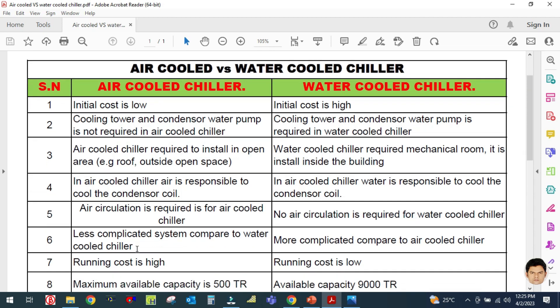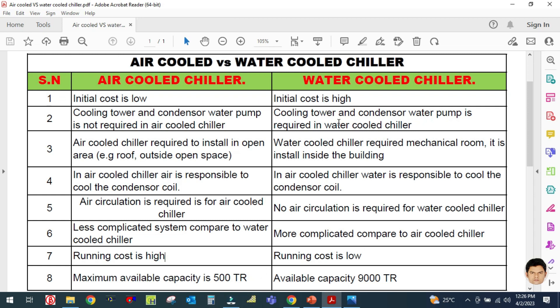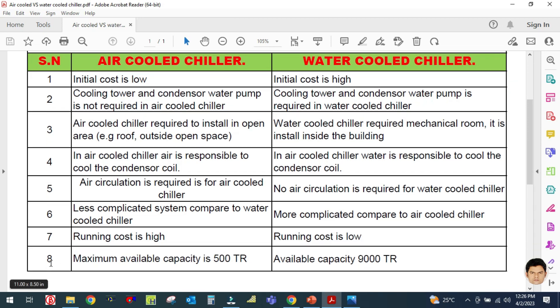The sixth difference is that the air cooled chiller system is less complicated compared to the water cooled chiller, because the water cooled chiller has a condenser coil, condenser motor, condenser cooling water, cooling tower, and more — making its network more complicated. Regarding running cost, the air cooled chiller has a high running cost but a low initial cost, whereas the water cooled chiller has a high initial cost but a low running cost, because water is used as the cooling medium.